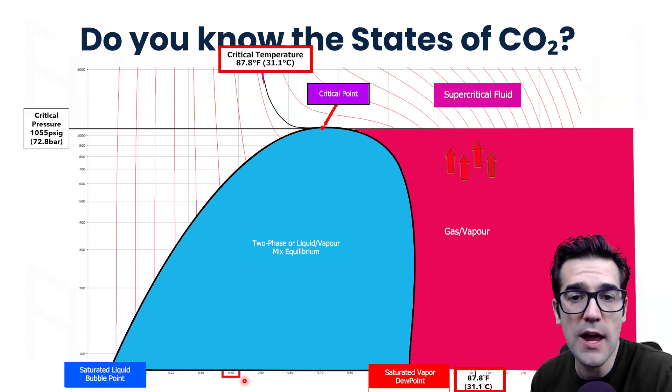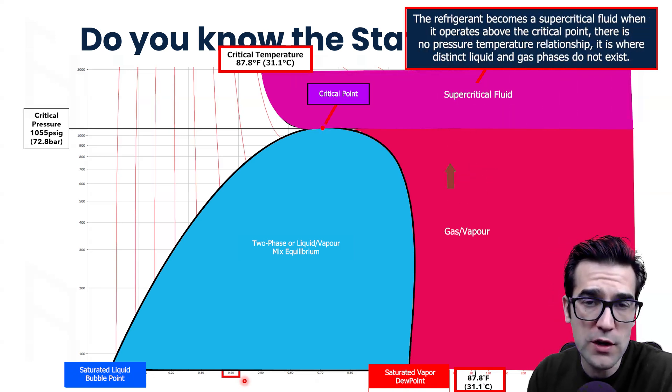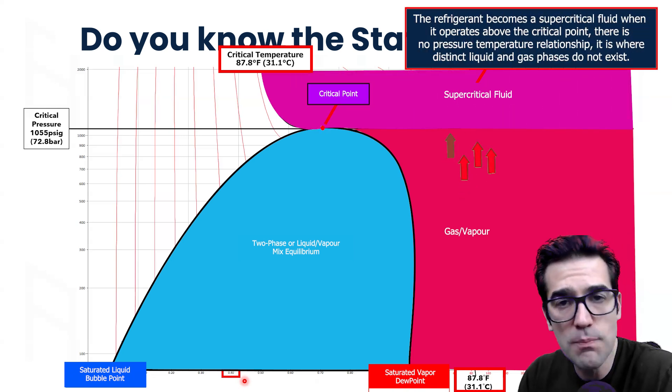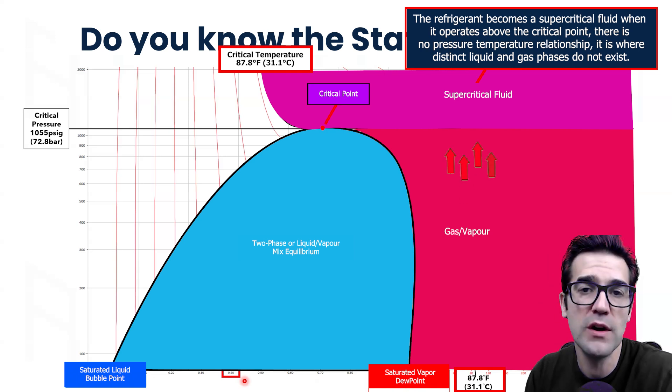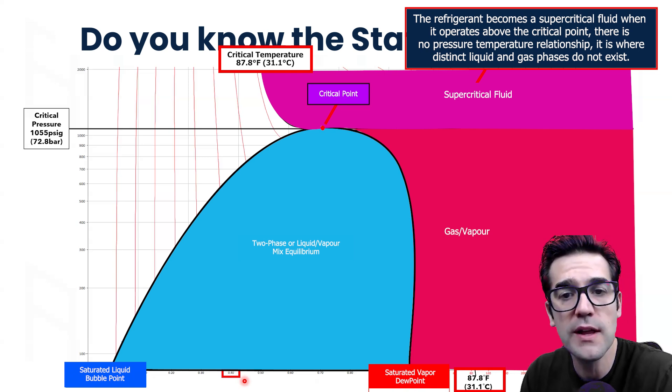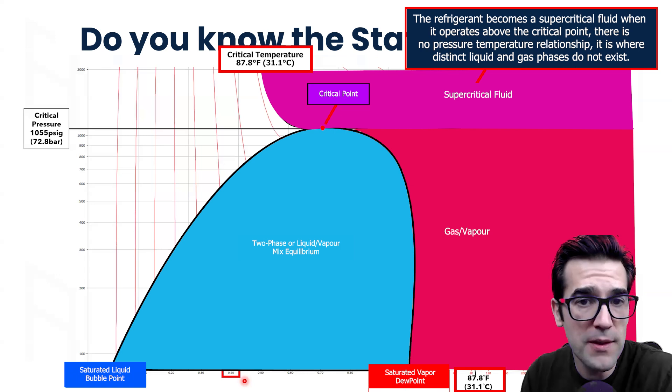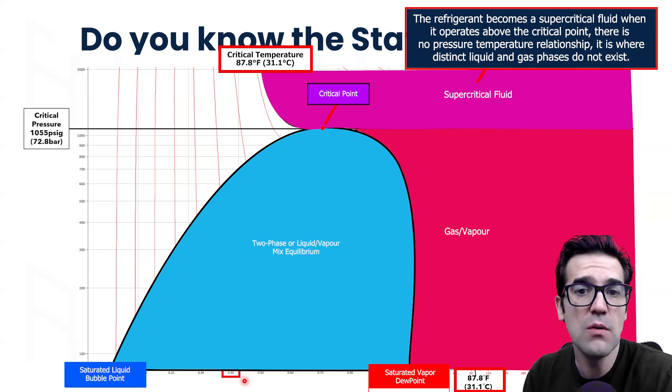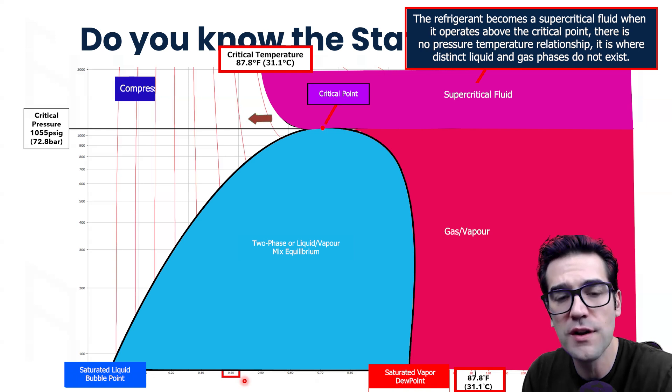From there, when we climb all the way up over the critical point, we are a supercritical fluid. This is where the transcritical nature comes from when we get into the transcritical cycle, because now we're running our system all the way up into a zone above the critical point, above the critical pressure, above the critical temperature. Now, we're a supercritical fluid.